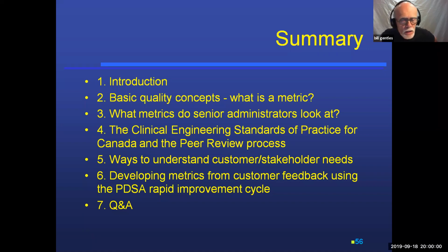A second one: we did a small quality improvement project where we got some data out of our CMMS on work orders where we were called to do a repair and there was no fault found. We could code that work order as a no fault found work order in the CMMS we were using. Now that, again, relies on your CMMS having a code that you can enter when someone asks you to fix something and there's nothing wrong with it. That's a very important and frequent cause of service calls to clinical engineering.